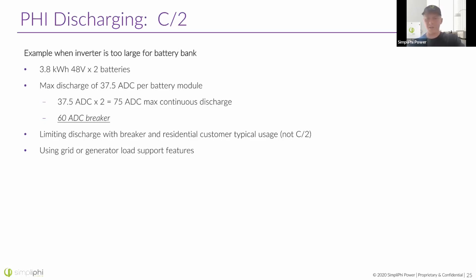So let's talk about this a little bit in more detail. Some other options here are using grid support or generator support. Several different inverters have this feature where you can program the generator to auto start as soon as the load reaches 3 kilowatts, for example. And you can do the same with the grid. It depends on your equipment's capability to actually do this.